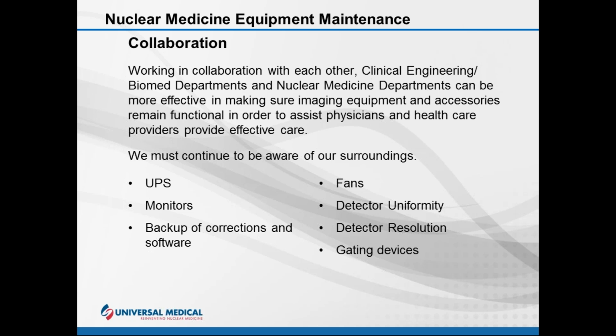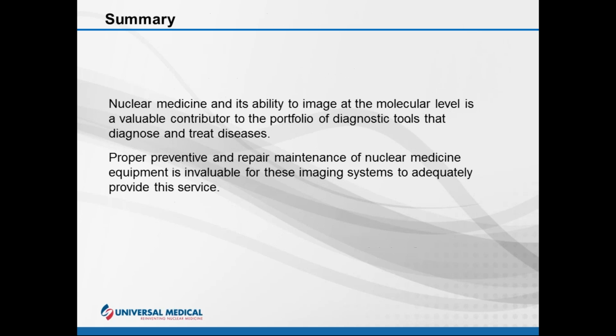Now, for those who are under the Joint Commission, the monitors in nuclear medicine, in CT, and in PET all have to be checked by a physicist once a year. That's a luminance test to make sure the brightness is correct, and also a test for resolution. Some of you, if you remember nuclear medicine way back, know what's called a SMPTE pattern. I always advise the technologists, if they have a SMPTE pattern on their system, never erase that off, because that is the image used to determine the resolution. That's very important to be aware of.